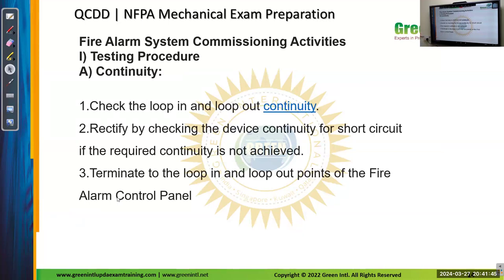So fire alarm system commissioning activities. What are the activities we will do in commissioning? Testing procedures. We will check the continuity. The loop in and loop out checking will be there. Rectify by checking the device continuity for short circuit if the required continuity is not achieved. Terminate to the loop in and loop out points of the fire alarm control panel. So what is this loop in and loop out? If you are connecting the fire alarm systems, we will check on 2 points, and we will check the continuity, whether the voltage or ampere passing is reaching the same or not, or if there is any leakage or any short circuit. So we will check on 2 different points.